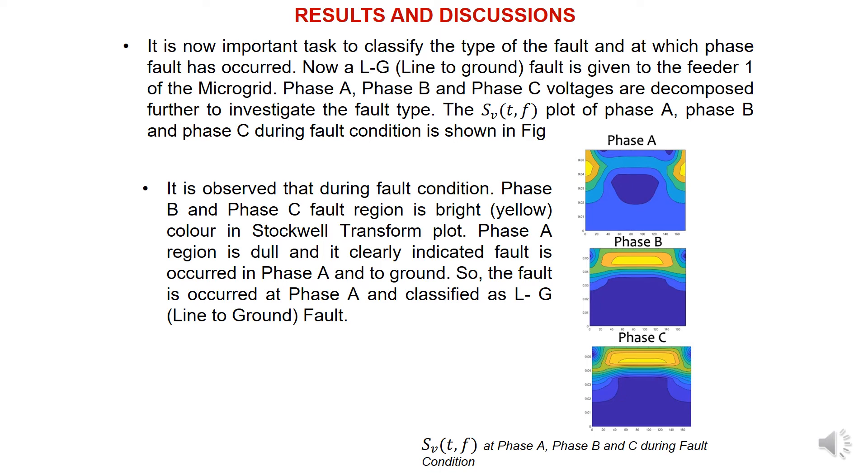Phase A, Phase B, and Phase C voltages are decomposed further to investigate the fault type. We are obtaining time-frequency plots from the Stockwell transform for all three phases during fault condition. It is observed that during the fault condition, Phase B and Phase C fault regions are bright, whereas Phase A region is very dull, clearly indicating that fault occurred in Phase A.